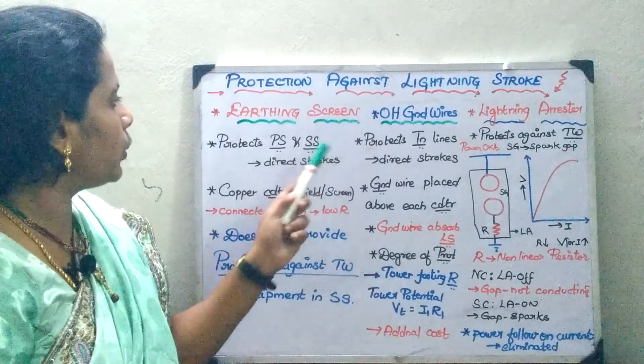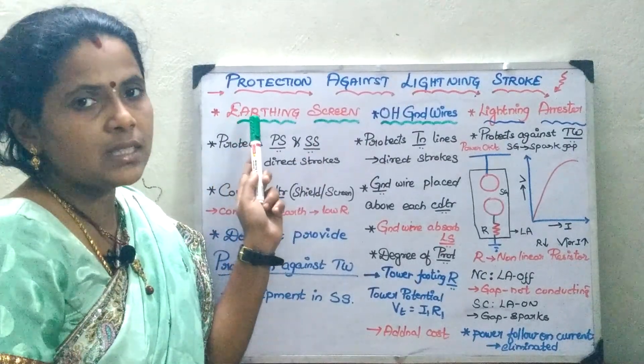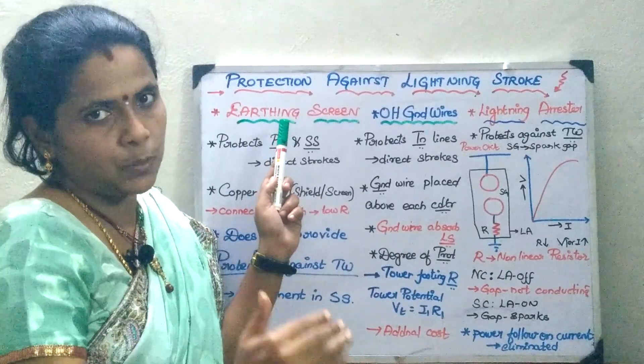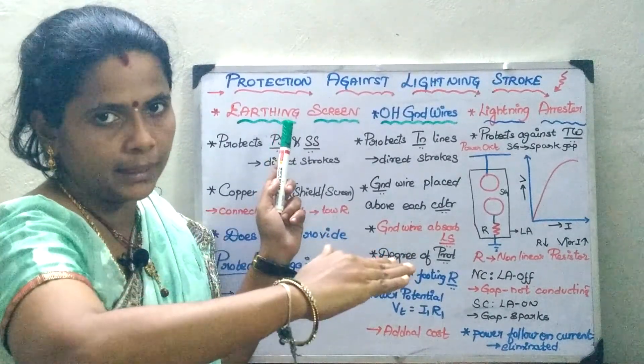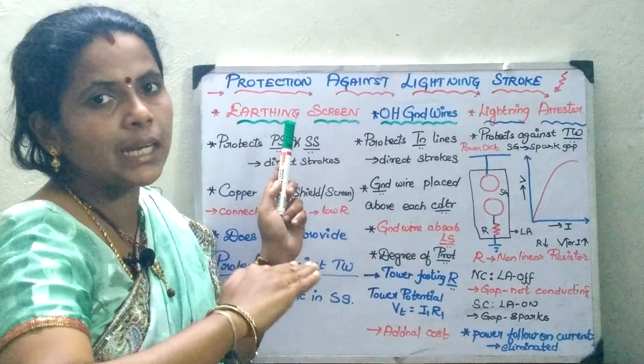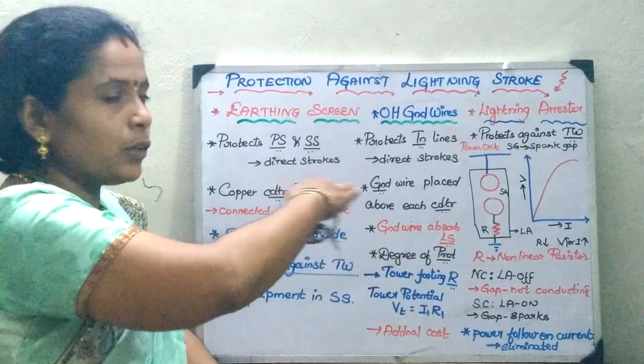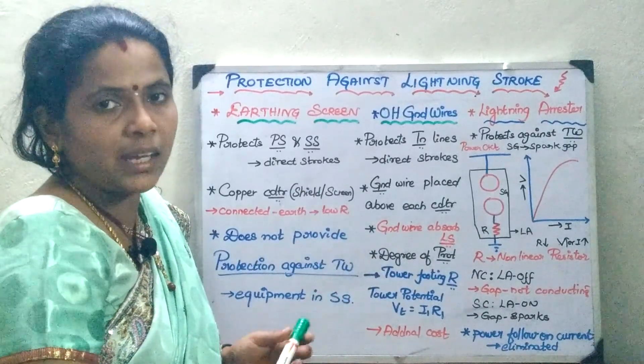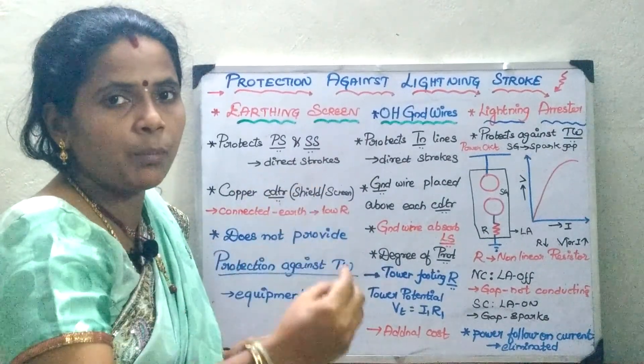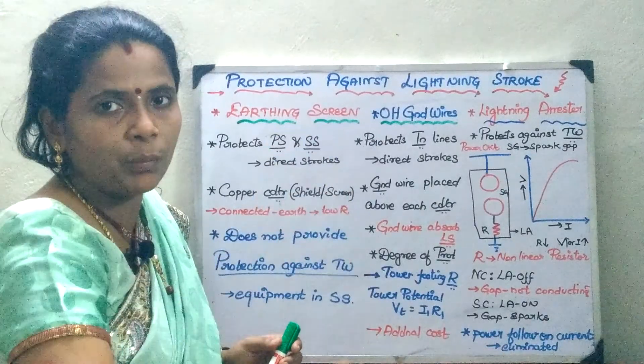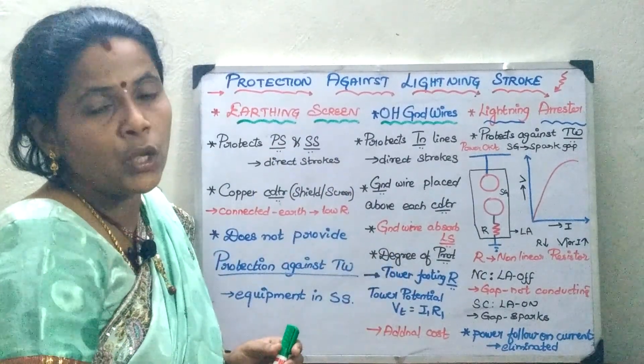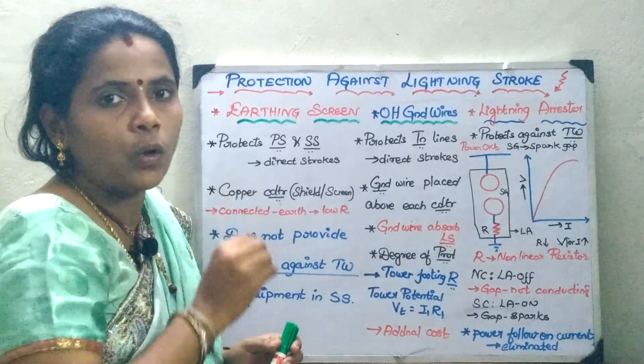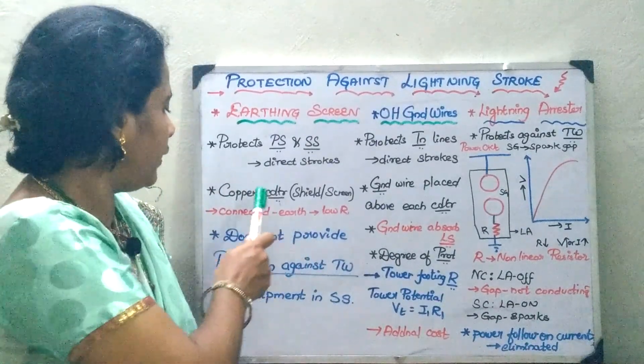The earthing screen mainly gives the protection to the generating station and the substation. You will have a copper conductor which is called as a shield or a screen, which is spread through the entire surface of your substation. In this case, at least two or three tapping points will be taken and it will be grounded, so that if a fault or a lightning occurs, through a low resistance path it will get grounded.